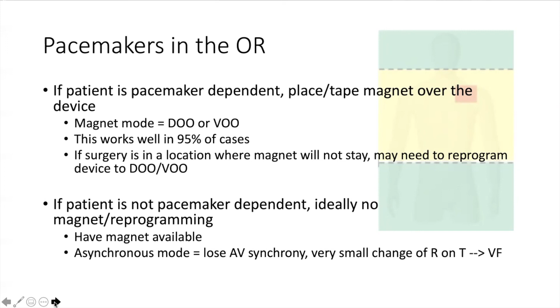However, if the patient is in a location where the magnet will not stay, like if they're doing cardiac surgery, you may need to reprogram the device yourself to DOO or VOO. If the patient is not pacemaker dependent, you really ideally want to do no magnet, no reprogramming. The anesthesiologist should have a magnet available, but in general, avoid asynchronous mode if you can. You'll lose AV synchrony, and there's a very small chance of R-on-T leading to VF. Low chance, but avoid if possible.